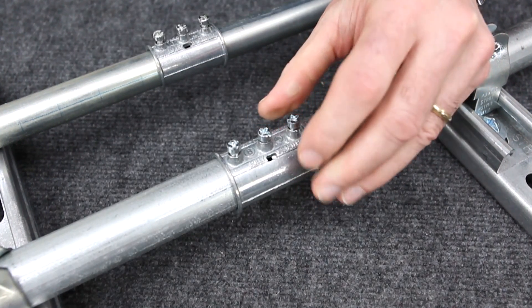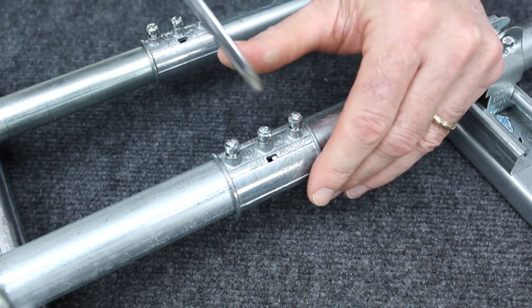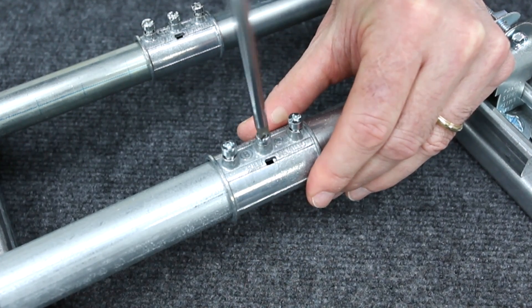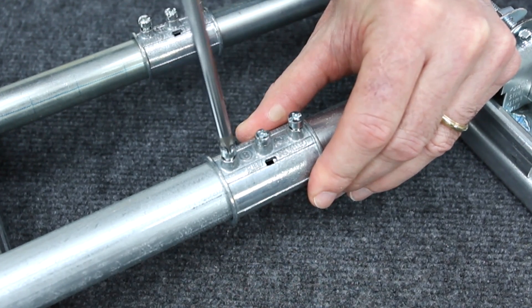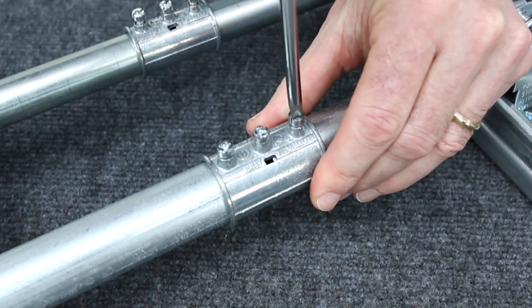To install a Mighty Align fitting, simply slide the coupling along the conduit until the conduit end is visible in the sight window. Drive the center screw to deploy the conduit stop and tighten the set screws. In seconds you have joined the EMT conduit.